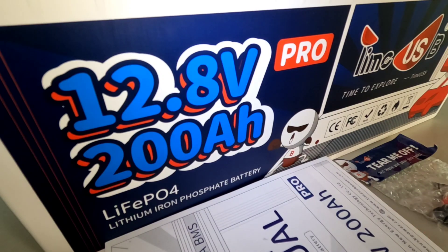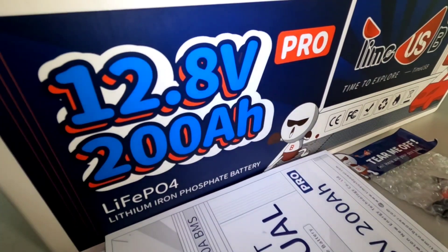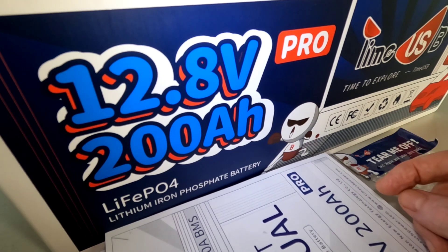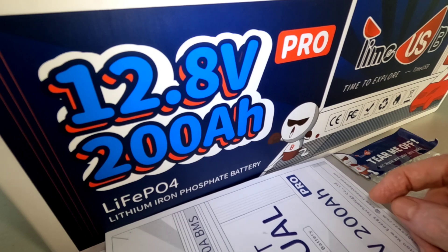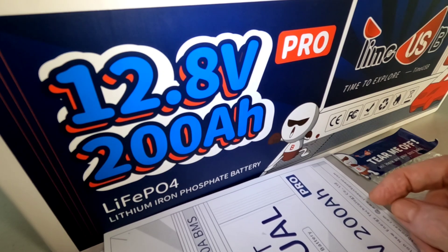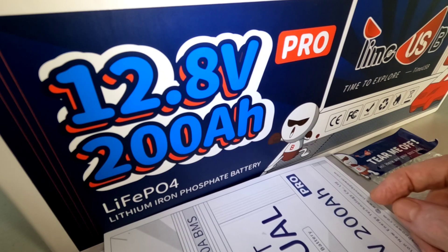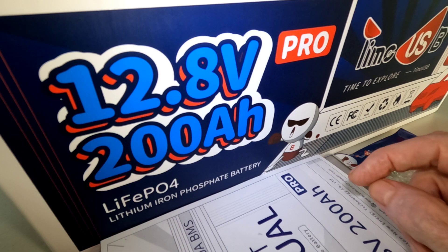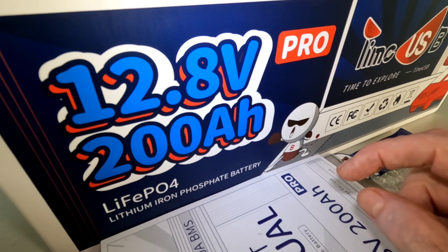On why they think it's a good fit: after being used for 1,000 to 1,500 cycles, the battery cell is a rigorous grade product designed and produced by CATL with better dust and humidity control and reliable quality. It uses 100 to 80 percent state of health in the EV bus, and the remaining 80 percent state of health will be used in energy storage applications. After being used in the bus, it is equivalent to a sufficient aging test in that stage, so the battery cell materials are stable in the remaining 80 percent state of health, giving higher safety and reliability.